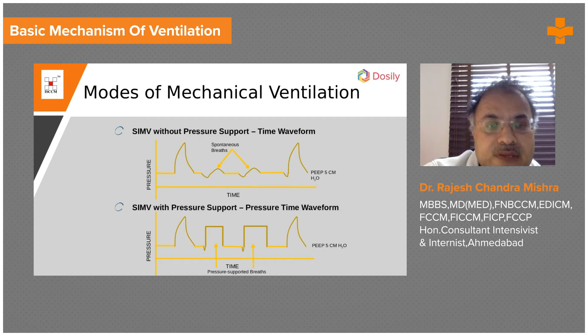Now what happened during this breath? The patient gets tired if not supported. So now SIMV is supported by pressure support. If you give support to the patient, the ventilator will give a breath if the patient is not triggering. If the patient triggers at the time of ventilation, then it will be a support mode, and that support you decide. So when you combine SIMV mode with pressure support, it becomes SIMV pressure support, where each spontaneous breath will be supported by a preset pressure. And if the patient does not trigger at a defined time, then the ventilator will give you its own breath which you have preset.